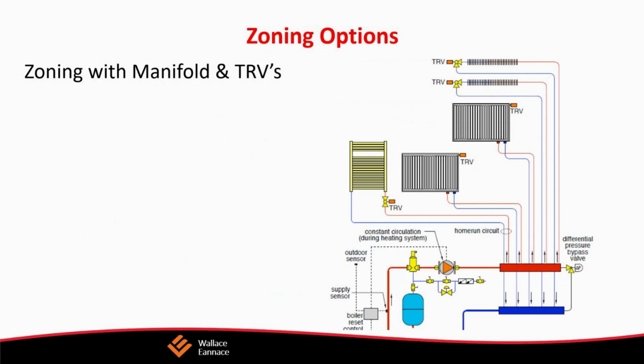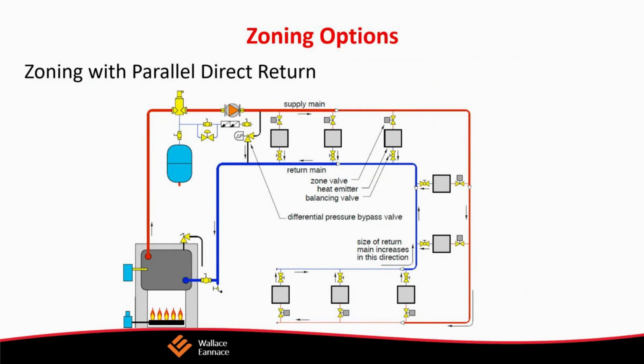One of the things is we talk about zoning a lot, and you can have thermostats and electronic controls, but sometimes you just have a simple zone over there, and the thermostatic radiator valves can provide a lot of benefit. They're non-electric, self-contained, they give great zoning capabilities, simple to operate. With these products, you set the desired temperature, and they modulate the flow into the radiator based on the ambient air temperature. They really save so much money that Con Ed and LIPA, for the most part, will give a rebate on these units whenever you're installing them, because that's how much energy they save.